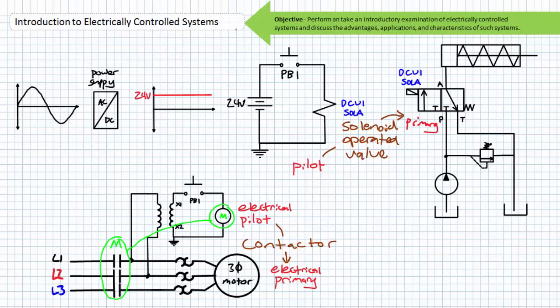Both primary devices, the contactor and the directional control valve, are the devices that actually conduct power. However, they do so only when their pilot devices, the coil in the case of the contactor and the solenoid in the case of the solenoid-operated valve, tell them to do so with a low voltage control signal. The contactor and the solenoid-operated valve are basically performing the same function, the establishment or interruption of primary power at the behest of a control signal.